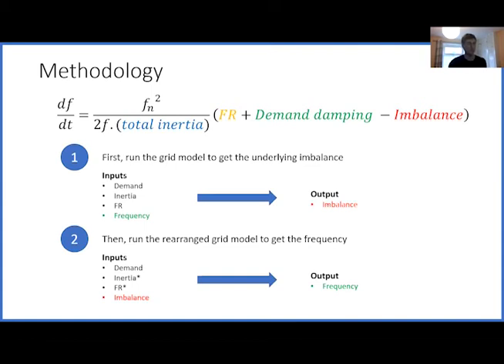So this is a bit about my methodology. On the top, you see the swing equation, which I've put into a grid model in MATLAB Simulink. What it's really showing is there's a fundamental link between rate of change of frequency on the left-hand side and power imbalance on the right-hand side. This power imbalance of the grid is made up of your fundamental imbalance, which could just be a generator tripping, giving you minus 1,000 megawatts straight away on the grid. Then your demand damping is a self-stabilizing property of the grid. And then you've got frequency response, which aims to counteract those imbalances that occur.